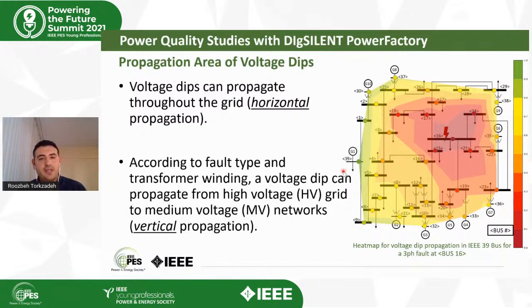Also, voltage dips can propagate vertically through the grid. It means that they go from one voltage level to another voltage level through the transformers. It depends really on the fault type and also the winding connection of the transformer. But actually, according to a study, about 30% of voltage dips that were experienced in the medium voltage grid were due to faults that happened in the extra high voltage or high voltage network. So this is also a thing to consider, because with this kind of heat map, we can see the horizontal propagation, but it's also important to consider that there would be a vertical propagation too.